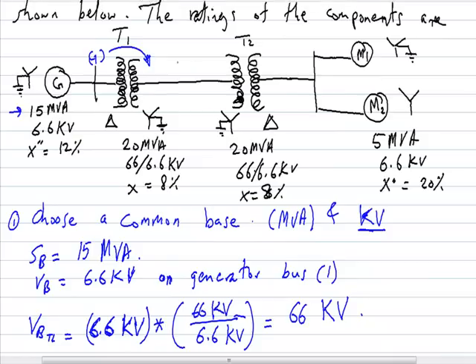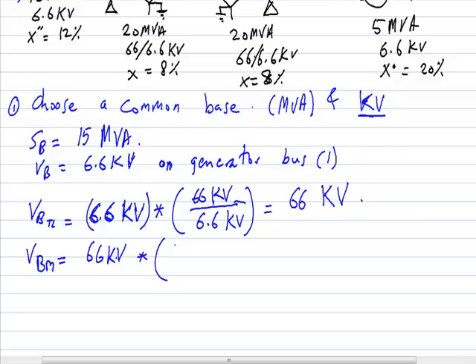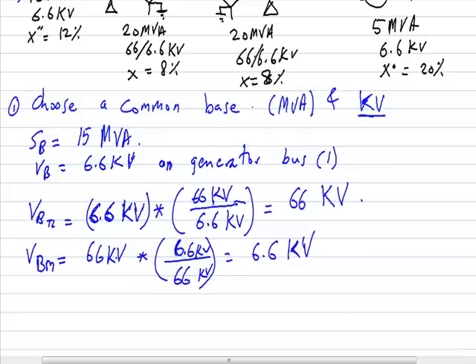Now the base voltage on the transmission line is 66 kV. I transfer this to find the base voltage at the motor terminals, V_base_M. V_base_M equals 66 kV multiplied by the transformer two turns ratio: 6.6 kV (secondary) divided by 66 kV (primary), which gives 6.6 kV as the base voltage at the motor terminals.